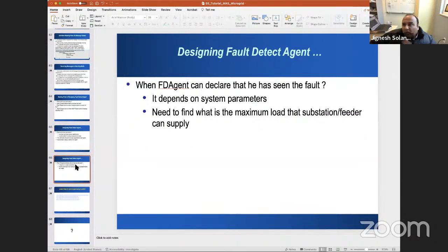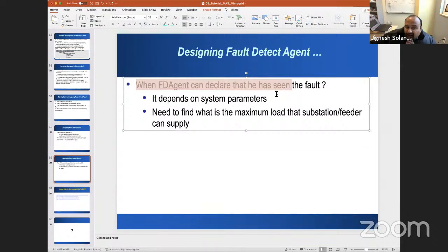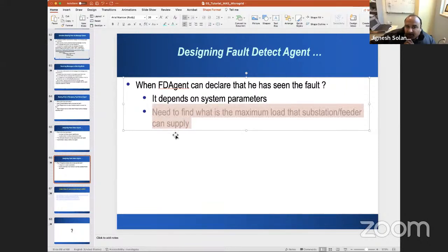When can the FD agent declare it has seen a fault? This depends on system parameters, but generally the current is 3 to 5 times larger than the largest load current—around 1.5 times the typical largest load current suggests the agent has likely seen a fault. You need to find the maximum load that the substation or feeder can supply.